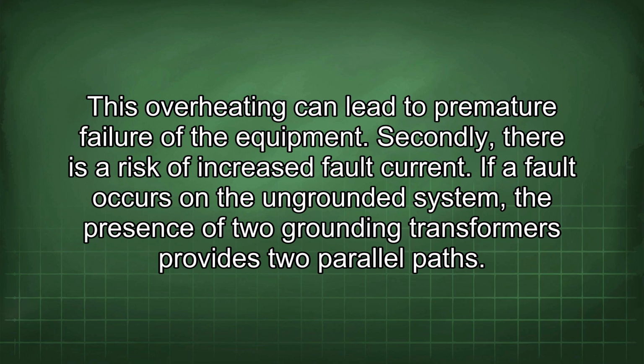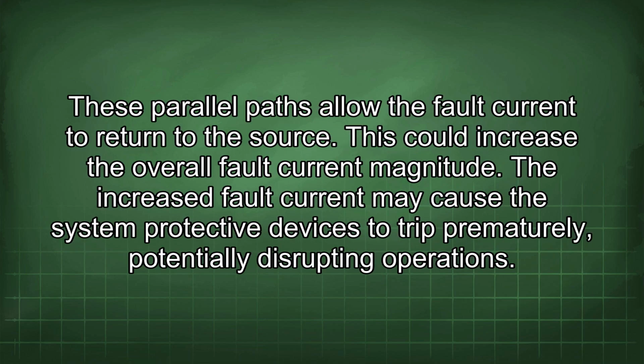Secondly, there is a risk of increased fault current. If a fault occurs on the ungrounded system, the presence of two grounding transformers provides two parallel paths. These parallel paths allow the fault current to return to the source. This could increase the overall fault current magnitude. The increased fault current may cause the system protective devices to trip prematurely, potentially disrupting operations.